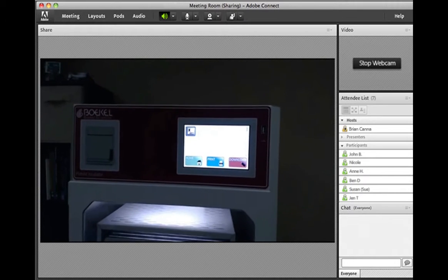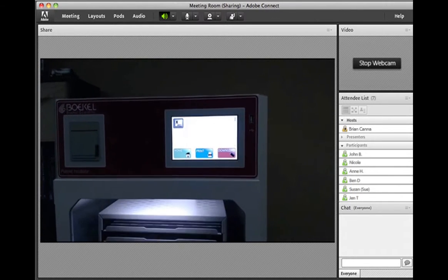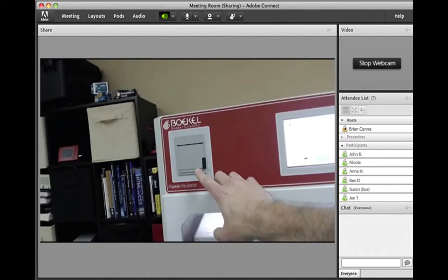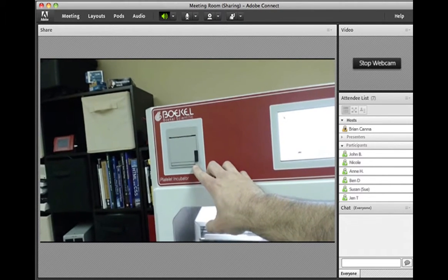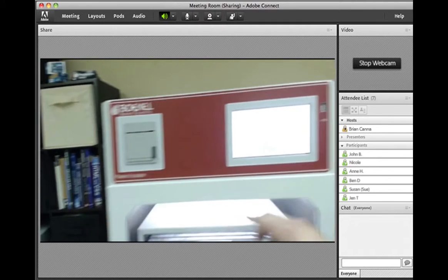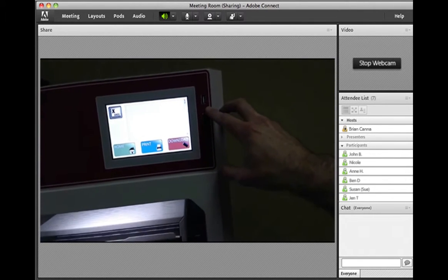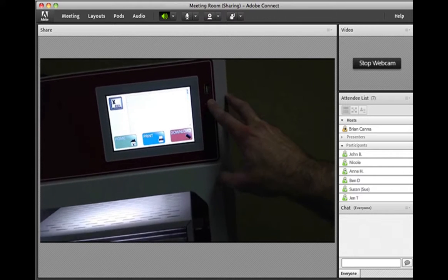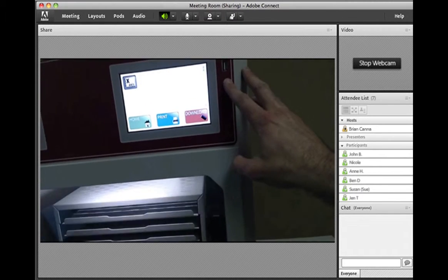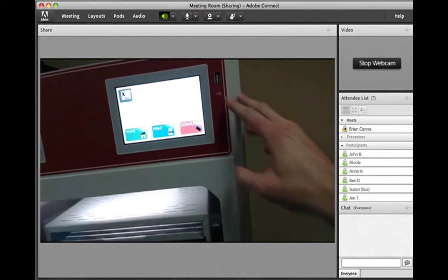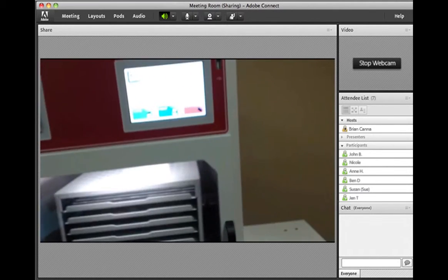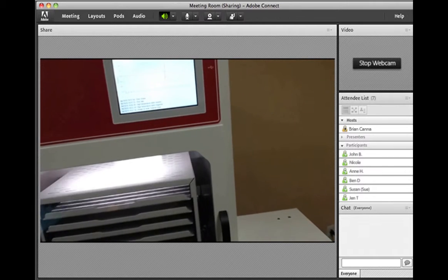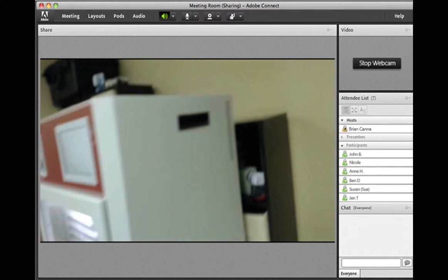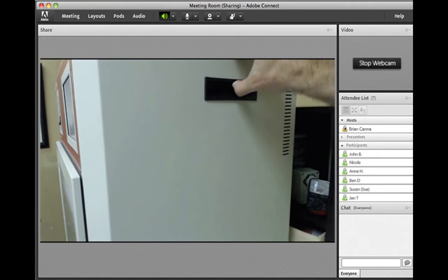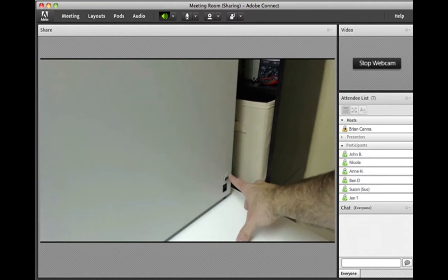So in the front of the unit we have a 7-inch color touchscreen for controlling the system. We have a thermal printer, and this prints out your temperature log and your event log. We have a USB port. This USB port is for downloading the temperature log, the event log, and for uploading firmware if there's ever a firmware change, and for any type of service. So it's multi-purpose. Around the side, we have a nice handle for actually lifting the unit up when you're placing it.